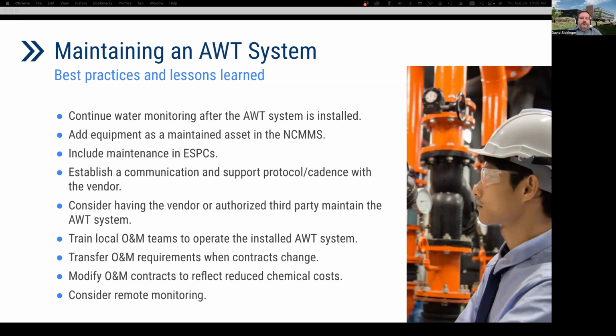And you want to include maintenance in ESPCs as well, which will be discussed a bit more by GSA staff. And then consider having the vendor or an authorized third party maintain the AWT system. The systems evaluated in this GPG report were successfully operated during the evaluations, but once the vendor was no longer involved, a few of these systems stopped working as designed. So again, having that ongoing communication and cadence with the vendor is good to maintain. Making sure the O&M teams know how to operate the installed system, and making sure that requirements are transferred when and if contracts change.